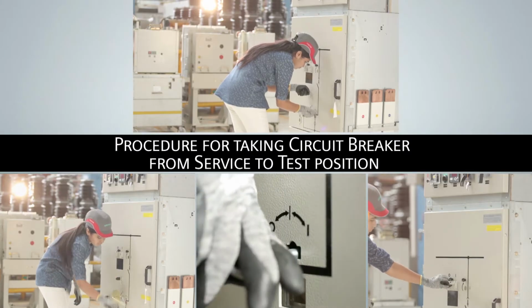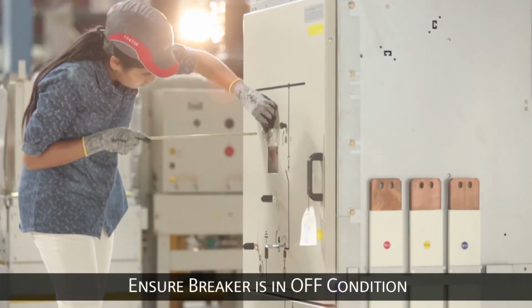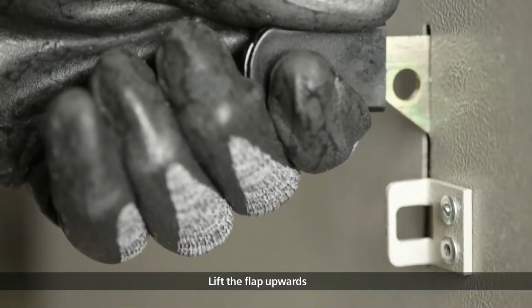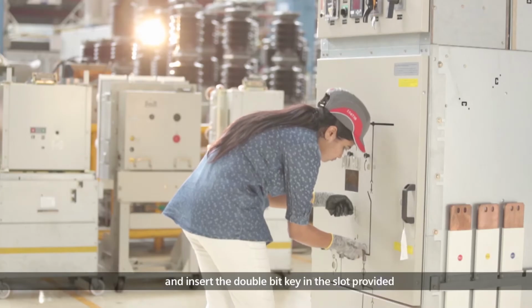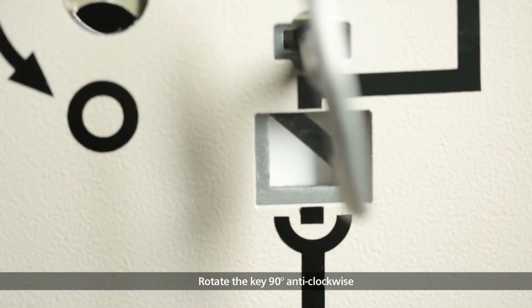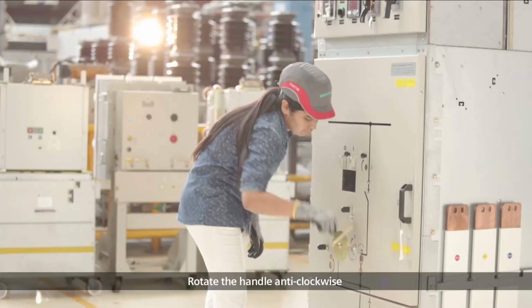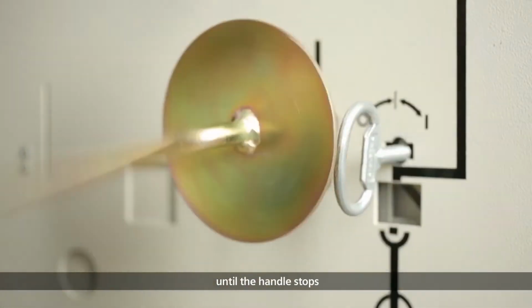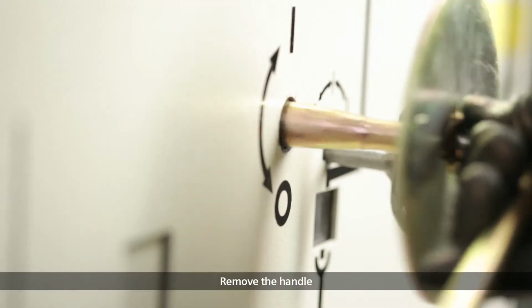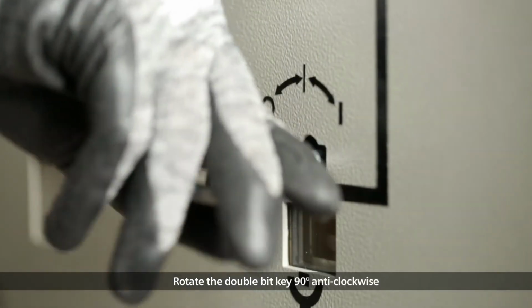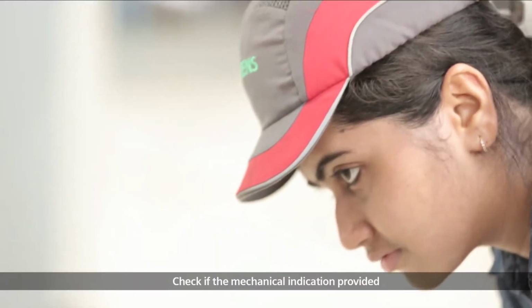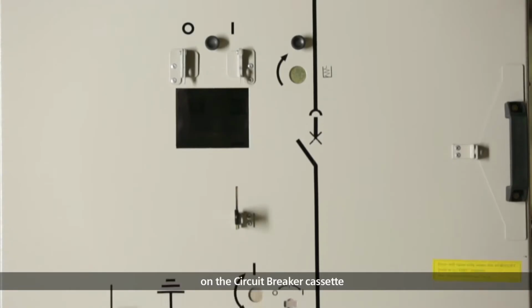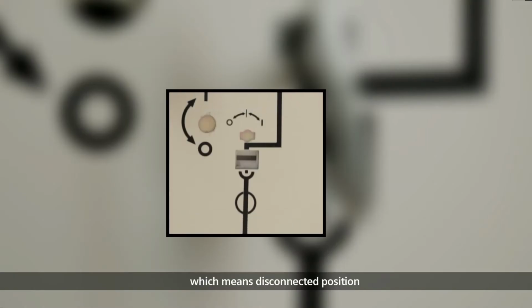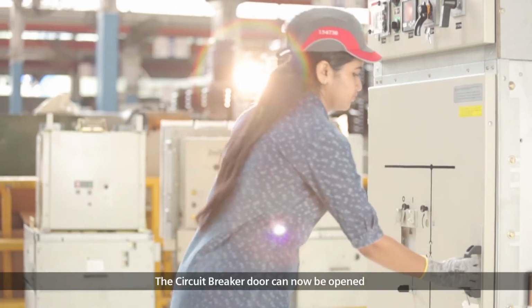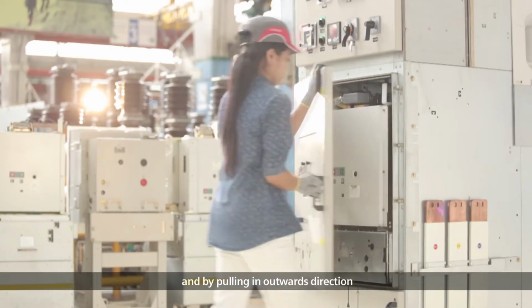Procedure for taking circuit breaker from service to test position. Lift the flap upwards and insert the double bit key in the slot provided. Rotate the key 90 degrees anti-clockwise and insert the circuit breaker racking handle. Rotate the handle anti-clockwise until the handle stops after approximately 18 rotations. Remove the handle. Rotate the double bit key 90 degrees anti-clockwise and remove the key. Check if the mechanical indication provided on the circuit breaker cassette is horizontal, which means disconnected position. The circuit breaker door can now be opened by sliding the handle upwards and by pulling in the outwards direction.